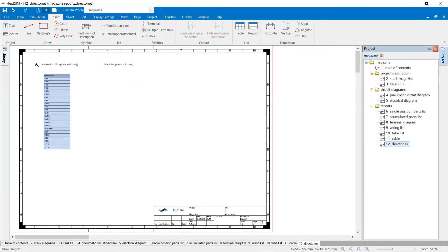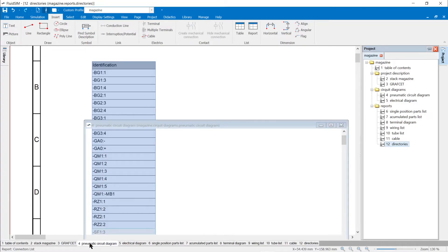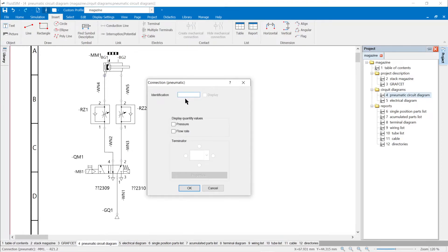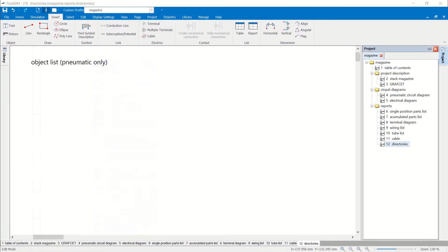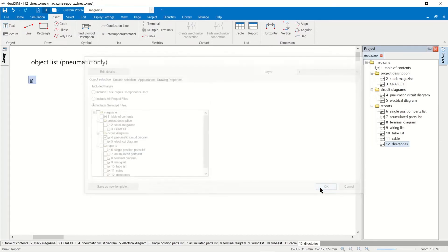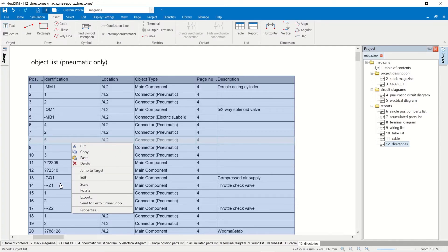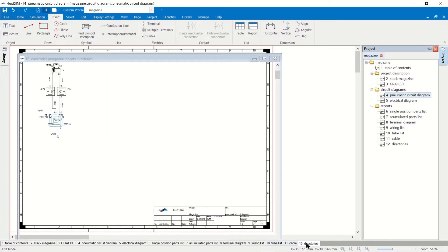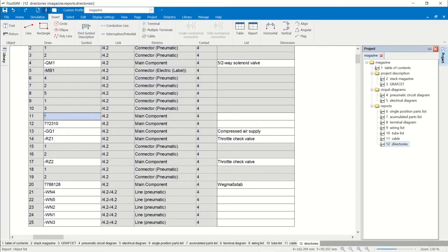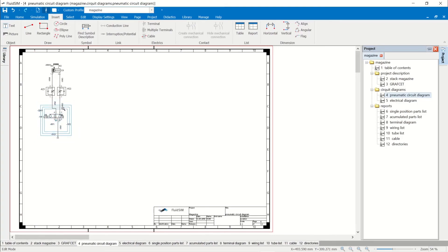Connections only appear if they have been identified in the pneumatic circuit diagram. In the case of components such as cylinders or compressed air sources, the connections in the component library have not been designated and must now be supplemented in the pneumatic circuit diagram. Once this has been done, the connections are also visible in the connectors list. All objects and connections of a circuit diagram appear in the object list. If undefined designations identified by leading question marks are to be found in the circuit diagram, you can right click on them in the object list and select the go to target command. The object is then displayed in the associated circuit diagram. The designation can be changed in the circuit diagram or in the object list. Right clicking on the designation in the object list and the command edit allows adding the correct designation. In this case, the silencers are designated RP1 and RP2.